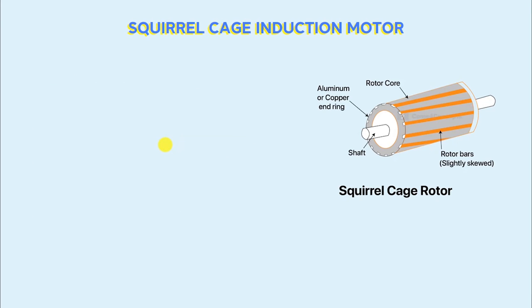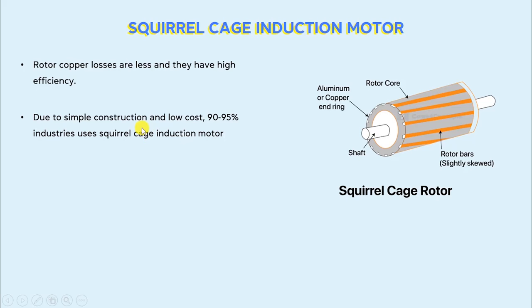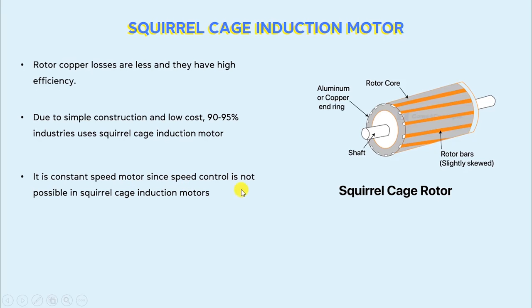Now let's discuss some of the advantages of a squirrel cage induction motor. The rotor copper losses are less in a squirrel cage induction motor and they have high efficiency. Due to simple construction and low cost, 90–95% of industries use a squirrel cage induction motor. Due to the absence of slip rings and brushes, they have simple construction and require less regular maintenance, resulting in low cost. Due to the absence of external resistance, the speed of the squirrel cage induction motor cannot be changed, so it is a constant speed motor.